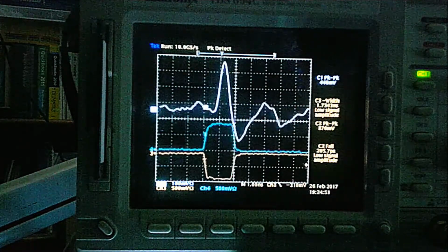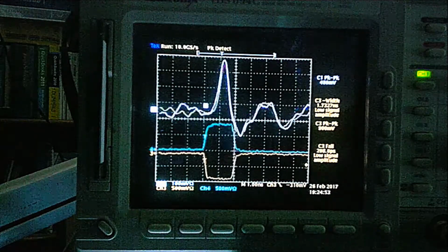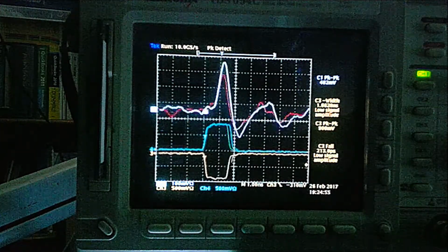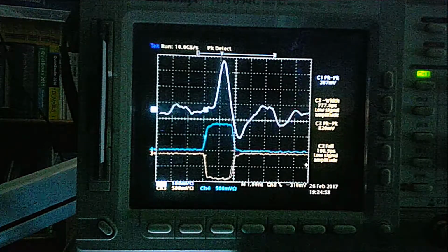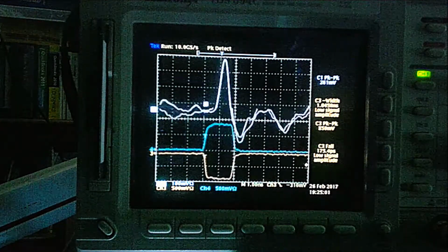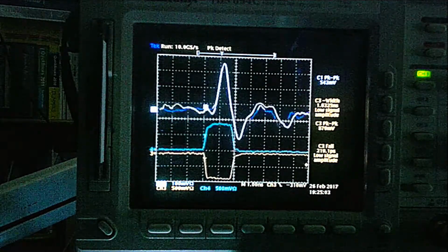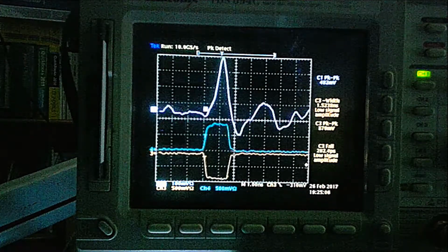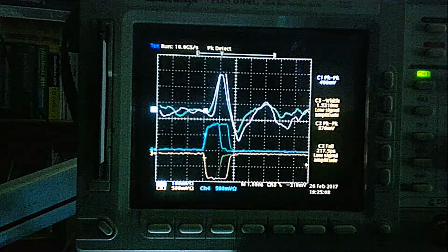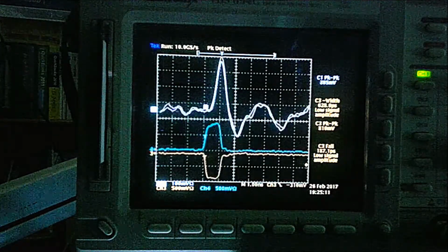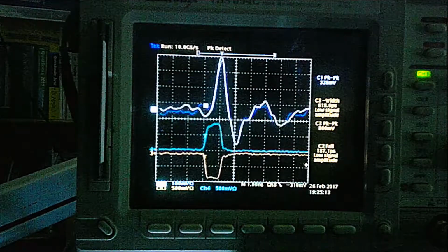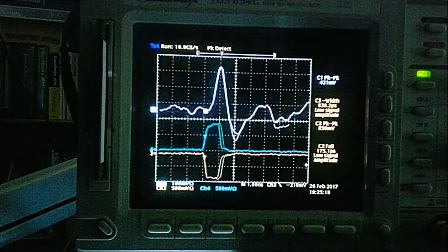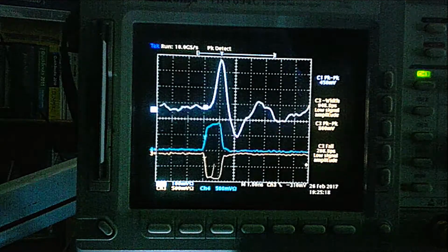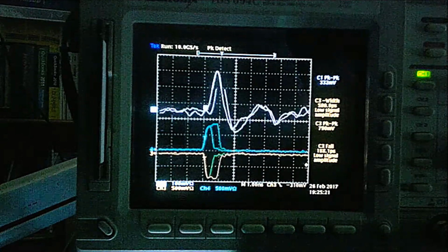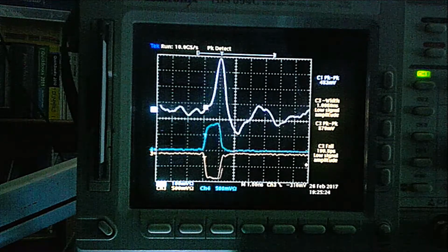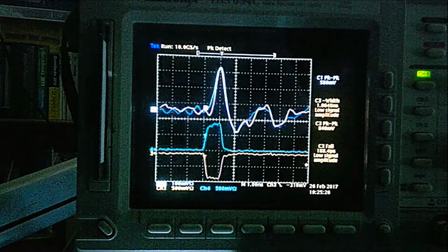This is not optimum. The output of the PV16 is too wide. I'm going to turn down the gain on the PV16 by adjusting the trim pot counterclockwise. It won't take much. When the pulse width is approximately 1 nanosecond for this particular tube, one has an optimum adjustment. The high voltage is set at minus 8,000 volts and the APD is set to 400 volts.